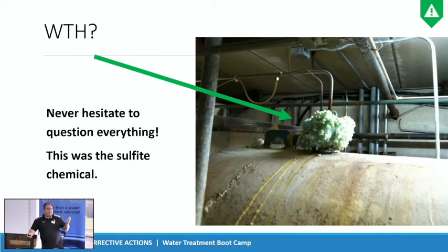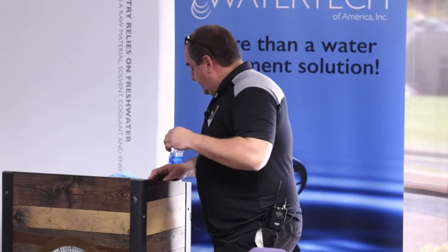I would say probably, especially on a boiler system, because a quill will inject it further into the water, whether it be 2 inches, 6 inches, or whatever the size of that injection is. Let me describe an injection quill. I don't think we have one here. It's like a big needle, a big needle that goes into a pipe or into a tank.